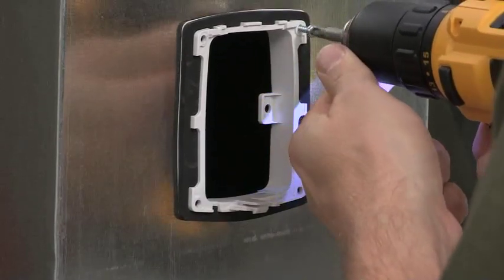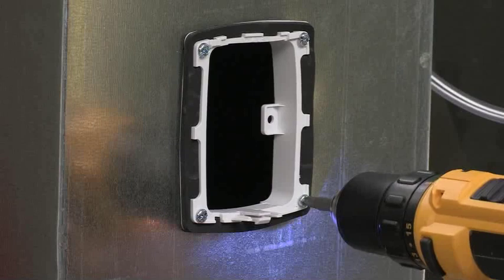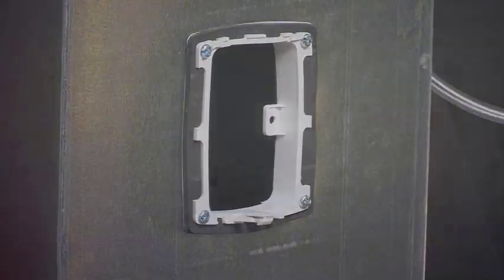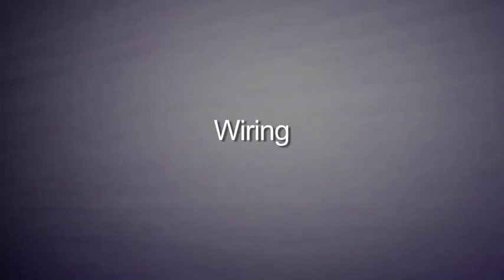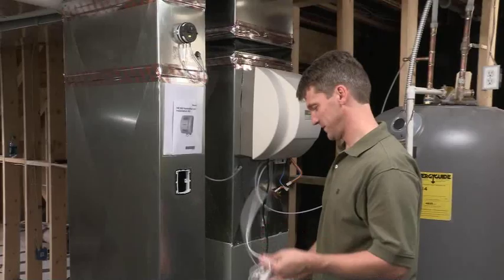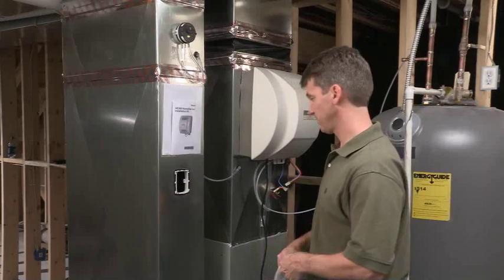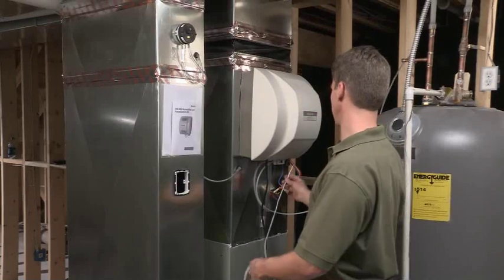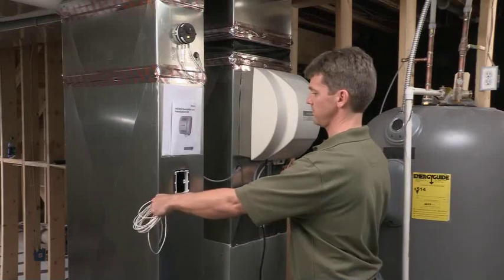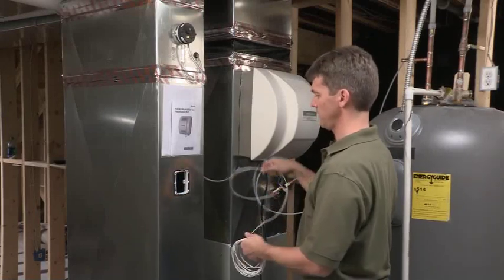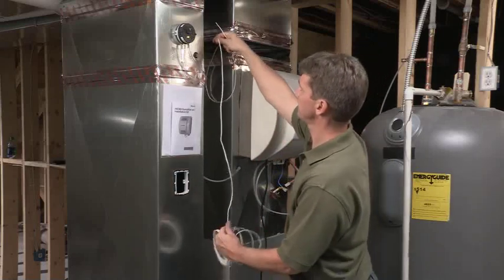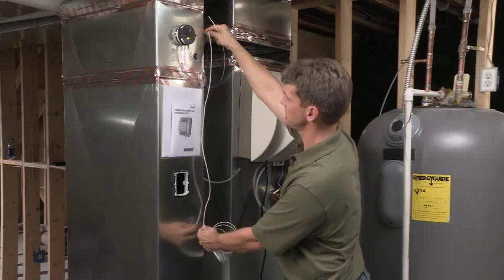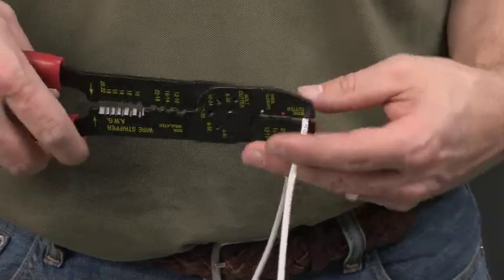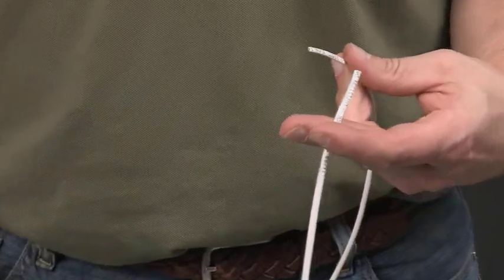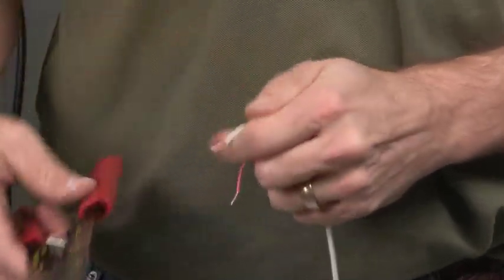Now, secure the base onto the duct with the 1-inch mounting screws that came with the humidistat. Now we're going to wire the unit. You can wire the components in any order you choose. Begin by measuring the wire from the humidifier to the humidistat and from the humidistat to the pressure switch. Cut the lengths of thermostat wire you'll need to reach between the components and strip the ends. Be sure to leave plenty of wire at both ends to make the connections.